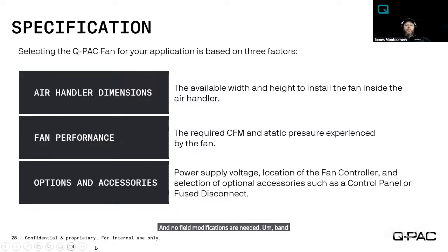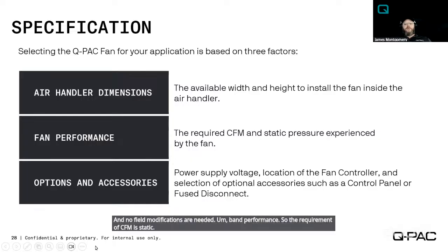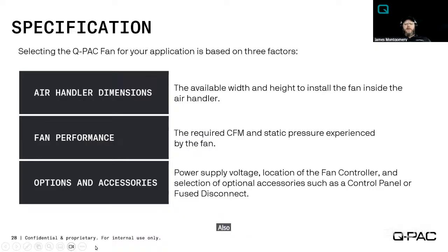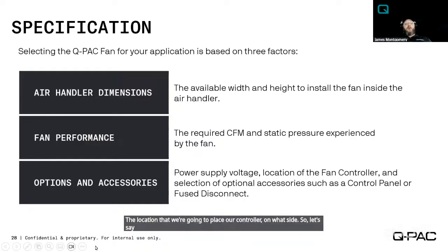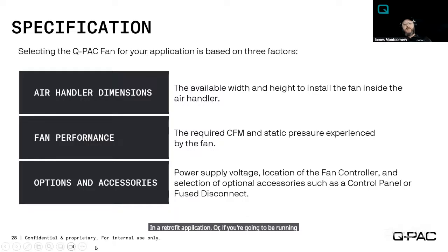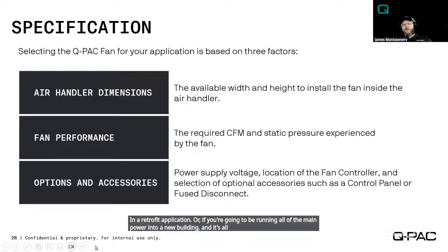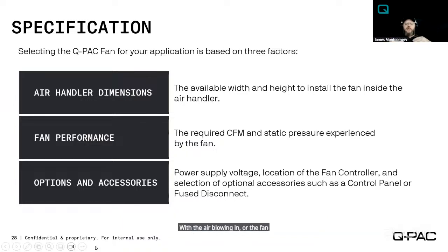Fan performance. So, the requirement of CFM and static. Those two things, sometimes there's a push-pull between them, but we need to know what your schedule is for your fan, what is your required CFM and static. Also, power. We need to know what kind of power you've got, and the location that we're going to place our controller on what side. Let's say you've got a controller that you need the power to come in on the left side because of where it is now in a retrofit application. Or if you're going to be running all of the main power into a new building and it's all coming from the left or the right side of the system, as we look at the fan with the air blowing in our face, then we need to know what side that's going to be on.